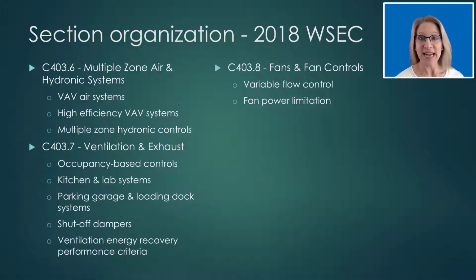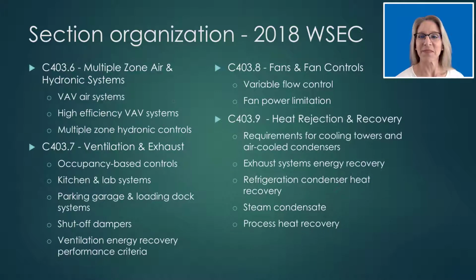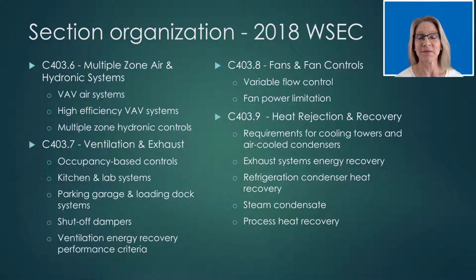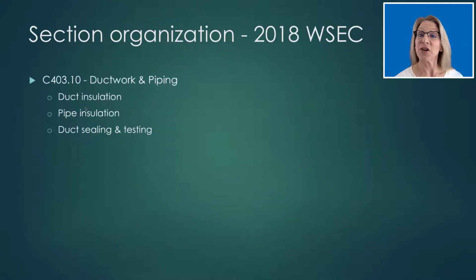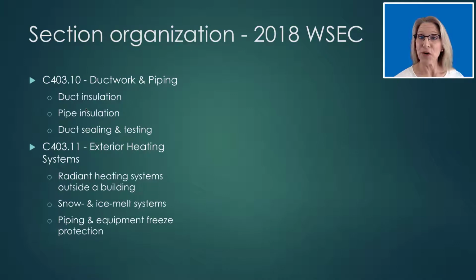Section C403.8 covers all other fan requirements, including the fan power limitation criteria. All of the requirements for cooling towers and air-cooled condensers, and all the energy recovery requirements for exhaust systems and for fluid systems, including refrigeration condensers and steam condensate and process heat, are all grouped together in section C403.9. All of the ductwork and piping related requirements are located in section C403.10. The controls requirements for heating systems that are located outside of a building, such as patio radiant heaters, and all the freeze protection control requirements, are in section C403.11.